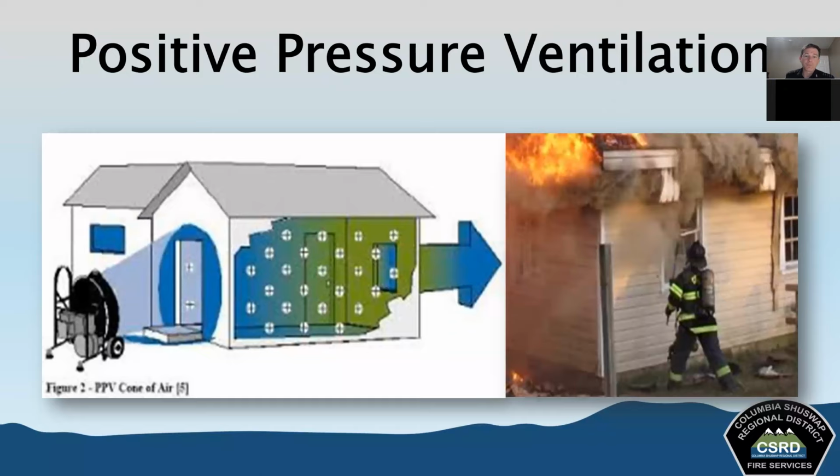If one is going to be opened slightly early, same as with natural, we're looking at the vent exit being opened slightly early. Same reason as the natural. If we open the vent enter, the inlet, early, you're going to be pushing that hot smoke and gases, and it's going to be looking for its own way out of the building, and those ways are going to increase the fire spread.